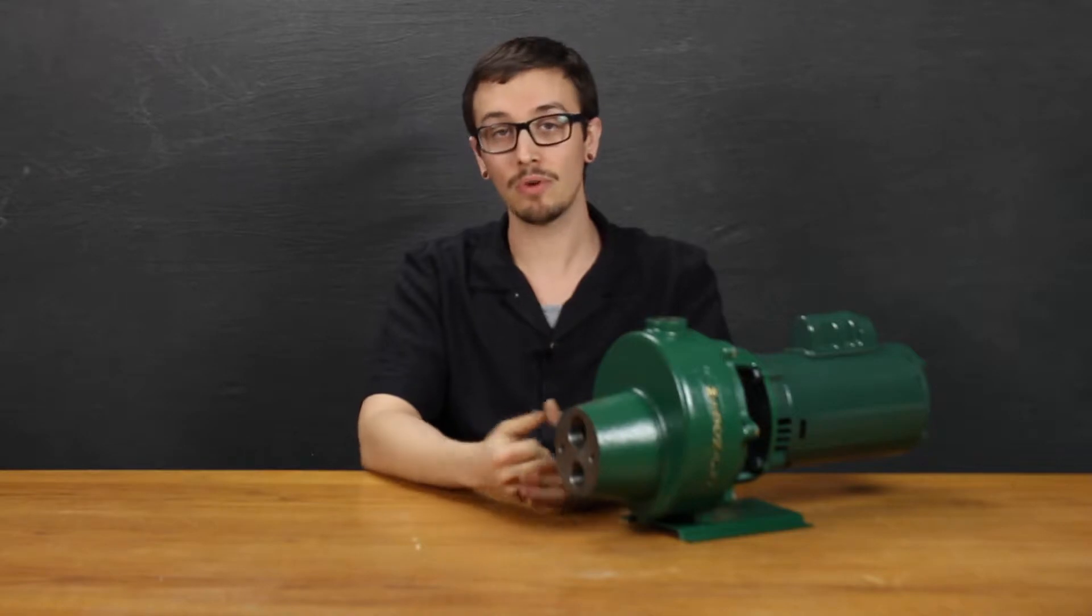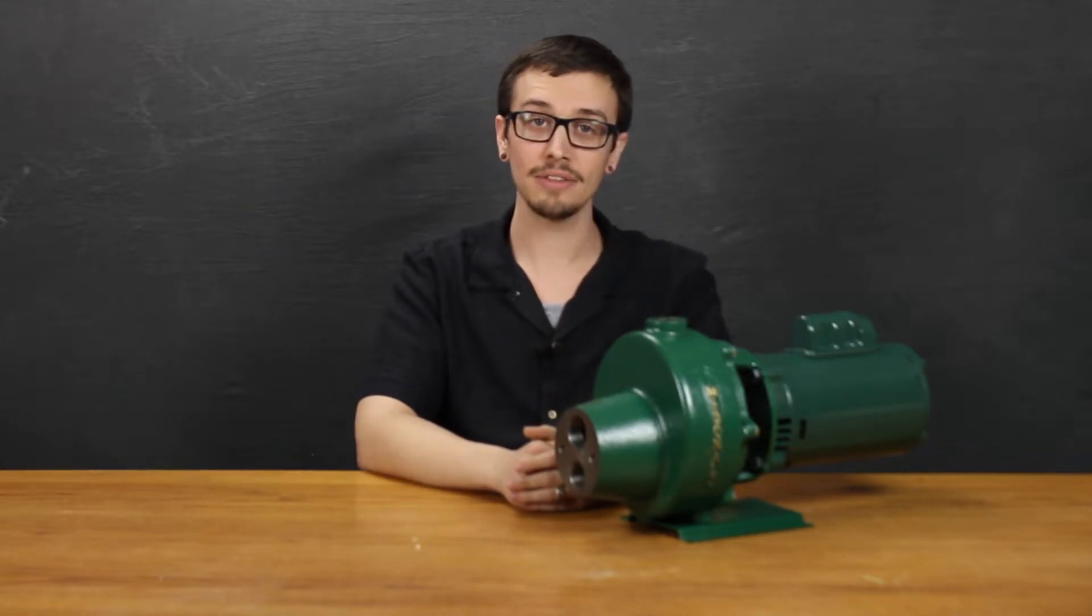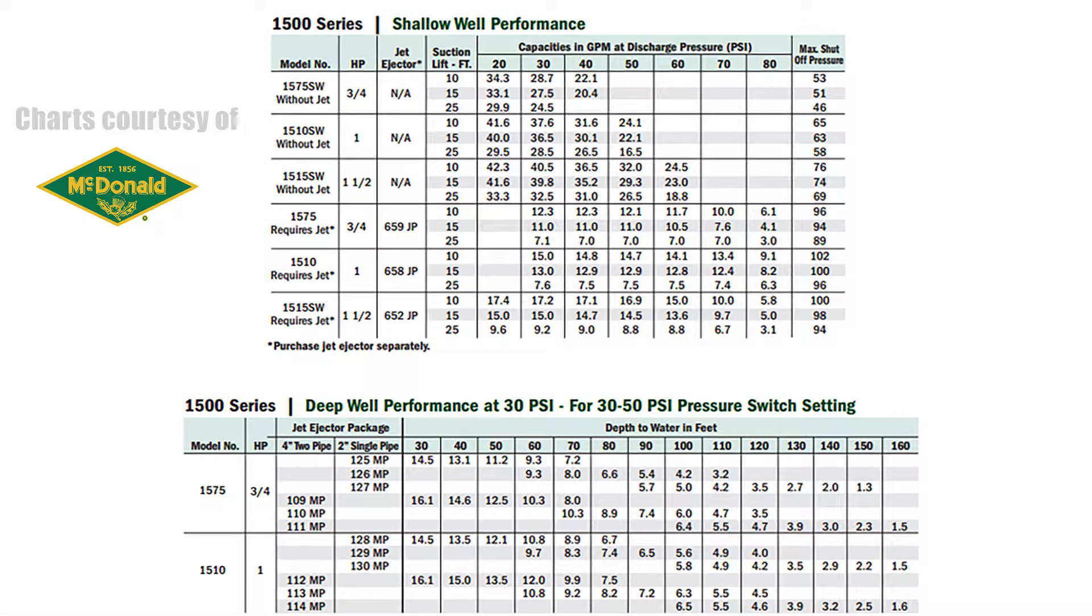In a shallow well, of course defined as 25 feet or less, the 1500 series are capable of producing up to 102 PSI with the addition of a shallow well ejector and 76 PSI without.